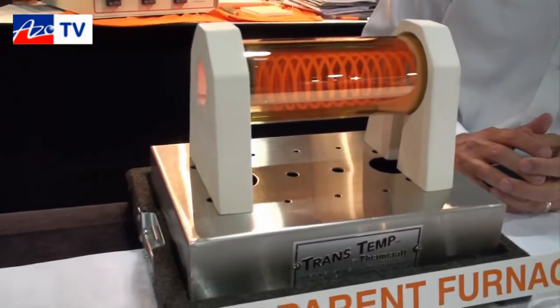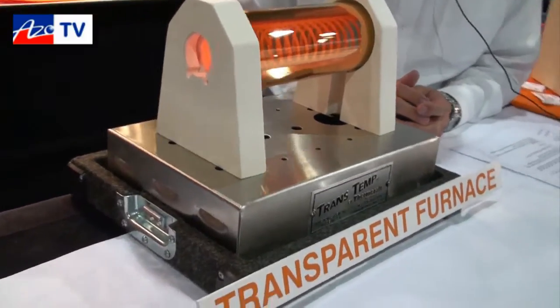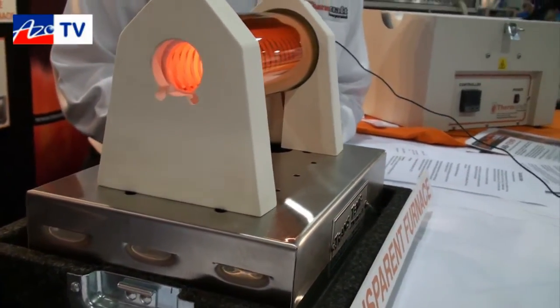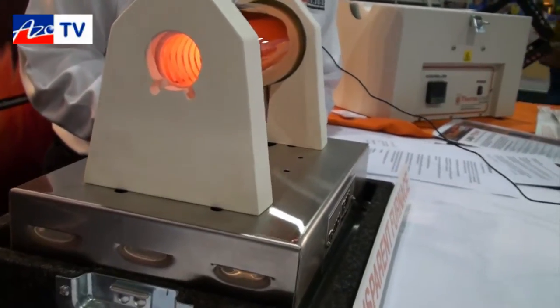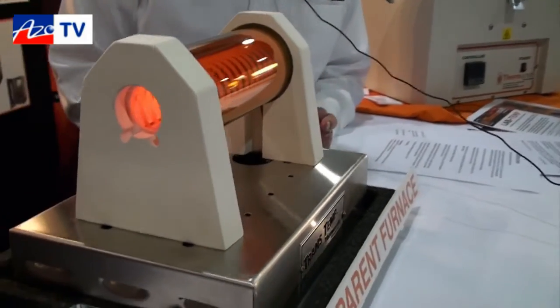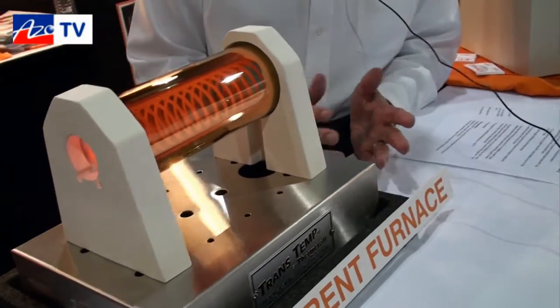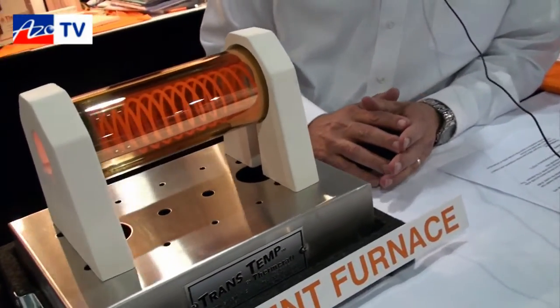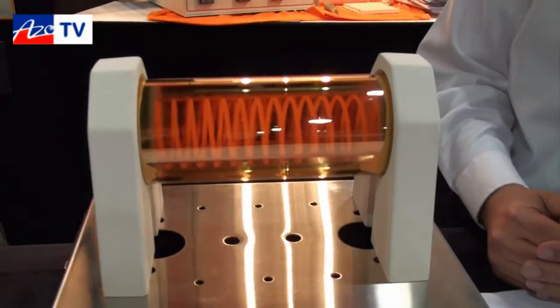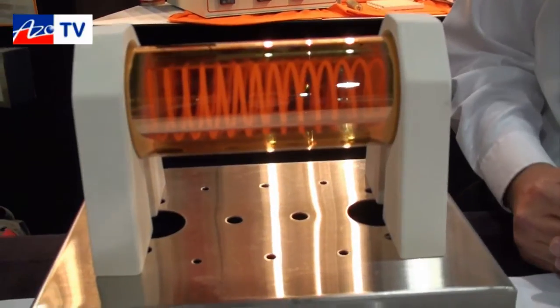It's made with a gold plating on an outer glass tube. There's a quartz liner inside to protect the gold mirror, and a cable heater — an electric resistance heater — that creates the heat. At about 600 degrees C, the gold film becomes transparent so you can see your process as it takes place inside the chamber.